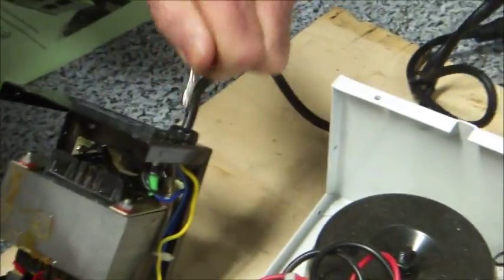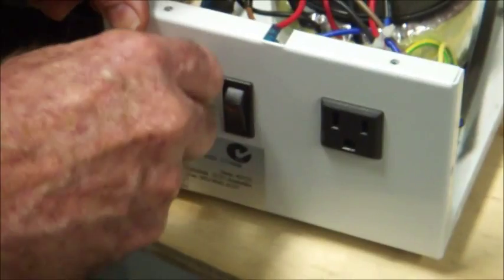Here you have a fuse holder which is not safe, I can put my finger in there. This one is an approved type, it's a safety type fuse, it'll come straight out. It's insulated, I can't get a shock in there by putting my finger in.